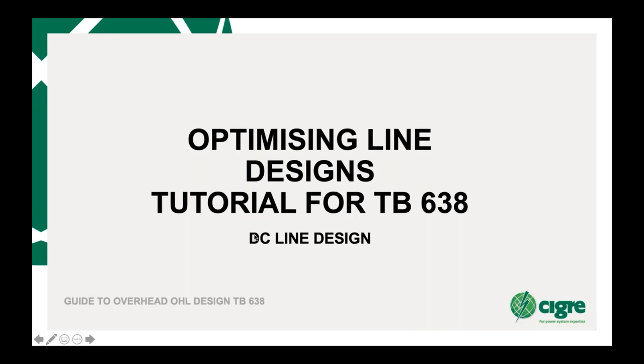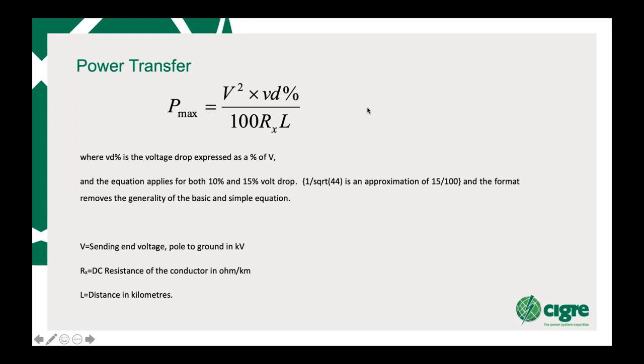Now we're getting onto DC line design. First thing we look at here is the electrical characteristics, and your maximum, now remember the other one was root of L over C. You're now looking really at a volt drop as a percentage of sending voltage. So this is an equation that they look at for the maximum power that will give you a particular volt drop of 10 or 15% for a particular DC resistance. And of course, it depends on your sending voltage, your length of the line, and the resistance in the conductor in ohms per kilometer.